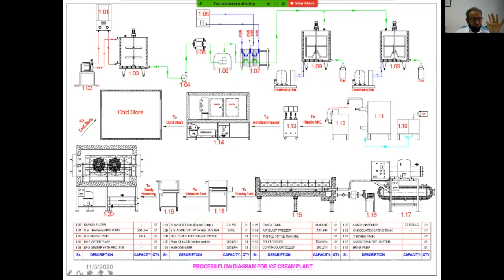It is certainly complicated, but as far as the refrigeration engineer is concerned, our refrigeration requirement will be here for cooling of the ice cream mix, then aging to maintain the temperature, then partial freezing of the ice cream, then final freezing of the ice cream, cold room for storage, and brine cooling. Let's go to the next.